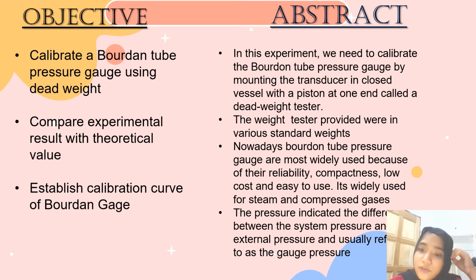The objective of this experiment is to calibrate a Bourdon tube pressure gauge using dead weight, to compare the experimental result with the theoretical value, and to establish the calibration curve of the Bourdon gauge. In this experiment, we need to calibrate the Bourdon tube pressure gauge by mounting the transducer in a closed vessel with a piston at one end, called a dead weight tester. The weight tester is provided in various standard weights.